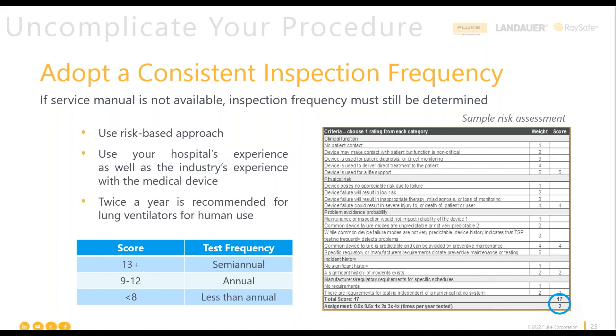In the quantitative analysis example, the ventilator scores a 17, which calls for semi-annual testing. This content is also available in our Advantage Training Center under the MDQA — Medical Device Quality Assurance — course series. Every chapter in that book is a separate course within Advantage Training where you can earn certificates of completion. It will help you figure out not only ventilators but many other medical gas flow devices you'll need to test. It's free, so there's no good reason not to do it.